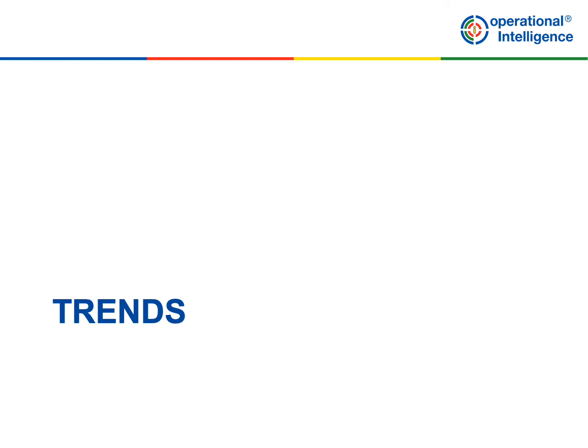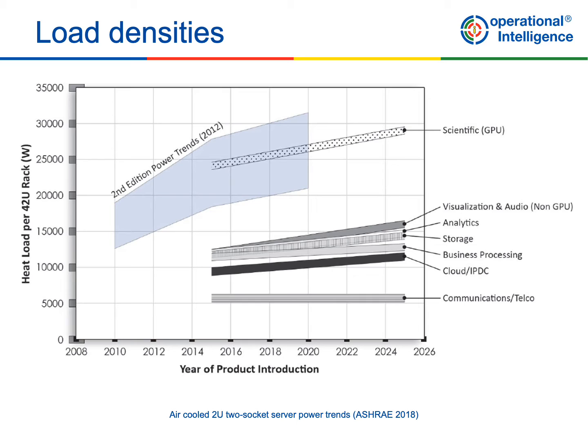Let's start by looking at trends in the industry. We see ongoing densification. So as computing performance increases, one of the impacts is an increasing heat load per footprint and also higher temperatures emitted from the IT hardware. It's necessary that our cooling systems design adapts to cater for these changing requirements.